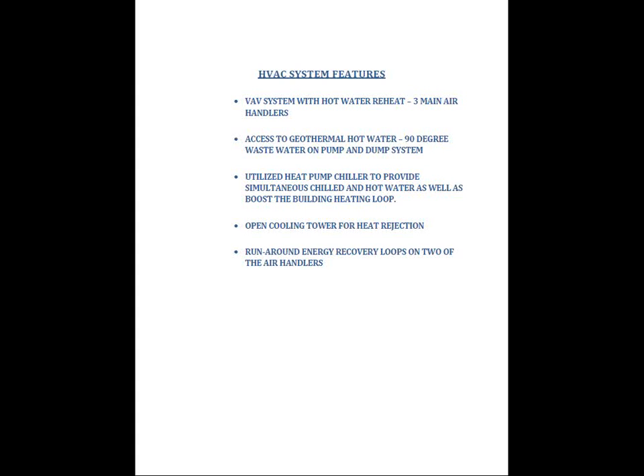Then I came across this heat pump chiller that's in the design. It provides simultaneous chilled and hot water, and it boosts the building heating loop. Basically, the system consists of the chiller and boiler in one unit. It's connected to a condenser loop, and then the condenser loop is hooked to the geothermal and the cooling tower. And then on the building side, you have your separate chilled and hot water loops. So obviously it was a system that I haven't ever modeled before. The cooling tower is easy to model. Then there are runaround loops on 2 of the air handlers, the ones that serve the shops. They have runaround energy recovery loops, which again, eQUEST doesn't do. eQUEST is air-based, so I had to figure out a way to do those as well.